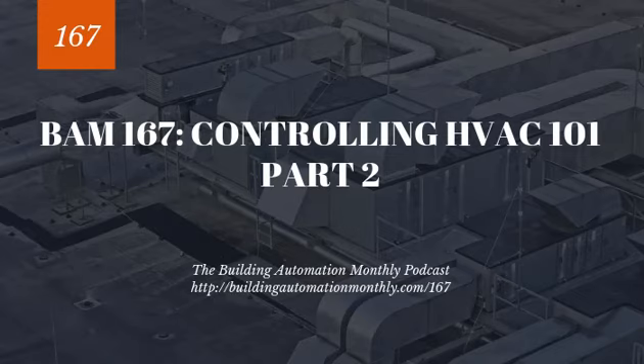Now they come in kind of two flavors. One that you'll see commonly with fan coils will be 3-speed fans: low, medium, high. Others are just constant volume, and they're balanced by the balancer, and they're set to provide a specific amount of airflow. And these are either direct to a space or to constant air volume boxes. Whereas variable speed, those tend to be for multi-zone variable air volume boxes. So that's where you'll tend to see variable speed fans.